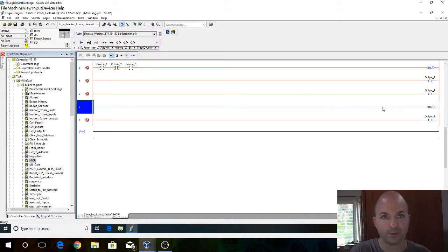Now, I don't have a simulator on this computer, otherwise I would show you how these things energize and de-energize and all that stuff. But regardless, what you can see here is basically when these three criteria here are met, it means the MCR is enabled. When the MCR is enabled, it allows passage to everything in the MCR itself. This output is outside of the realm of the MCR, and so it's going to work like normal. It has no bearing on what these three criteria are doing.